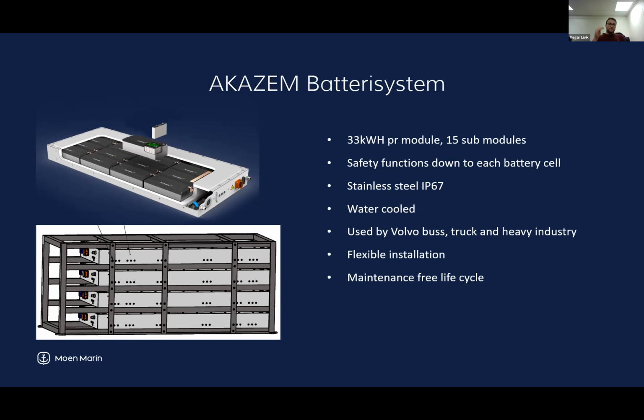We're now on generation 2 of the modules. The first vessel had generation 1, which was 24 kilowatt hours per module. Now we're on generation 2, at 33 kilowatt hours per module, and we're already helping develop generation 3, which will be 98 kilowatt hours per module. So the modules are getting bigger, energy density is increasing, but the total cost per kilowatt hour is going down. Where a normal installation might have 10 modules, in two years' time we may only need 3 or 4.